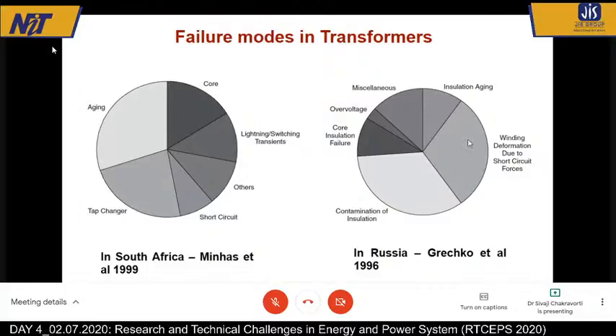And on the right-hand side, if you see another study done in Russia, here a large chunk is written as contamination of insulation. By the way, contamination is not necessarily external contamination. It could be the result of aging. And here again, you can see insulation aging stated separately. So if we take these two, it is almost 50%. So it is quite obvious. And then there is core insulation failure also. It is quite obvious that insulation is the primary weakest link in the failure of the transformer.